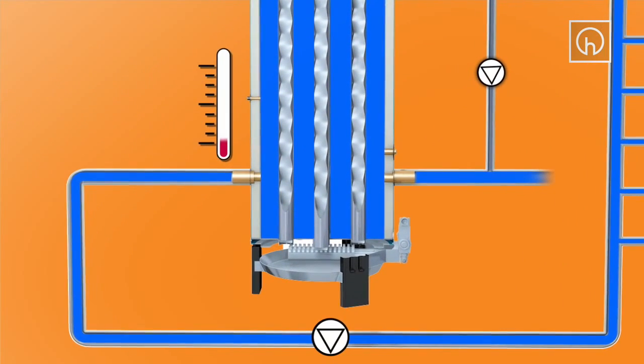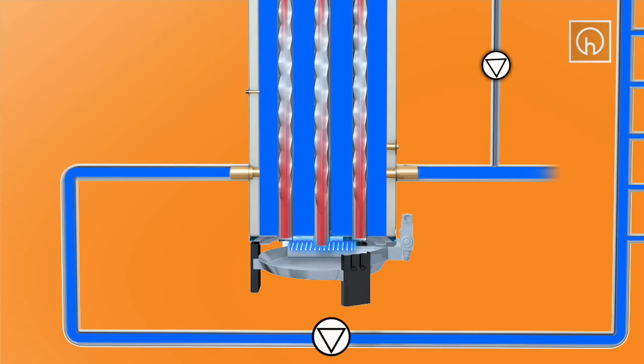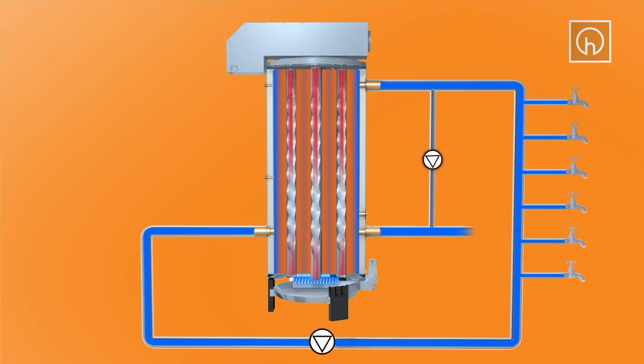The temperature sensor within the tank signals that the water is cold and ignites the burner to start heating. Hot gases from the burner pass up the tubes and the temperature of the water close to the tubes increases. A flue baffle within each tube improves heat transfer, increasing operating efficiency.